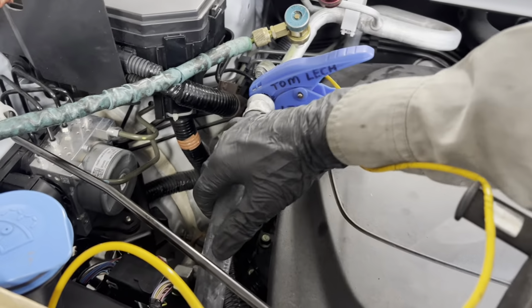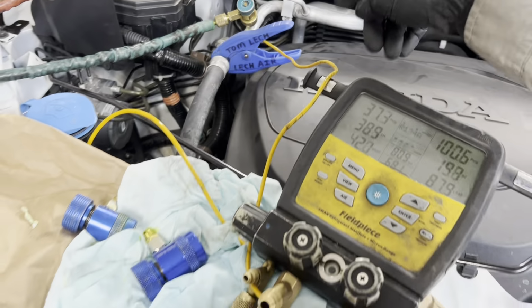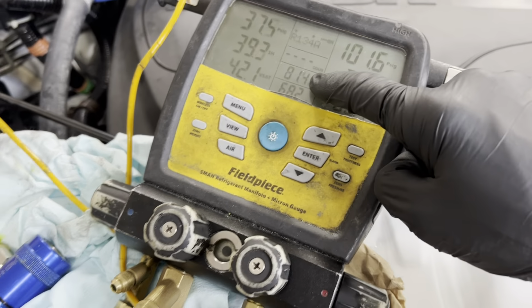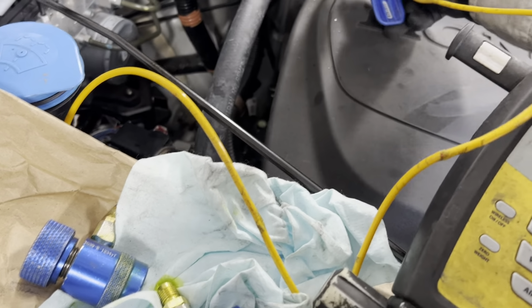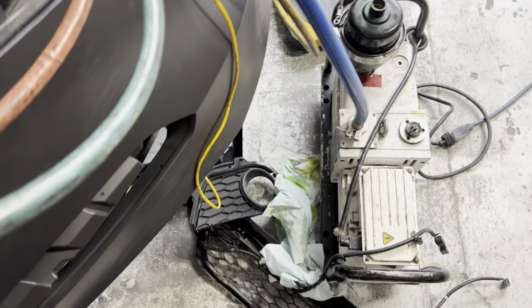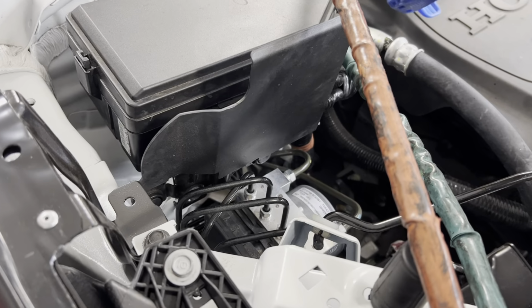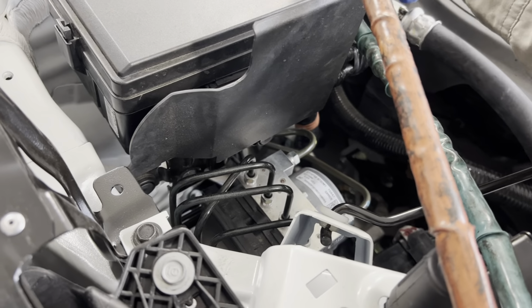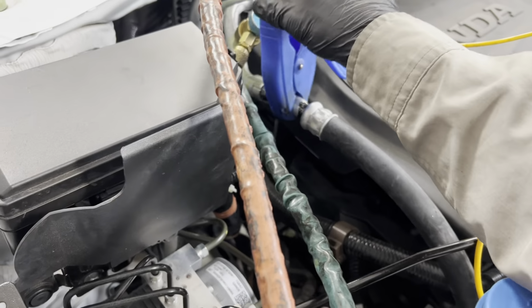What else can I show you? Here we're at the other end of the heat exchanger picking up heat from right here, which is 81 degrees. So if I could take this, let's put this right here, and let's take this properly. I'm gonna get my other sensor over here. This one here was not supposed to be on the high side line, it's supposed to be on the suction. So if we put it on the suction right here, okay, we're on the suction right there.